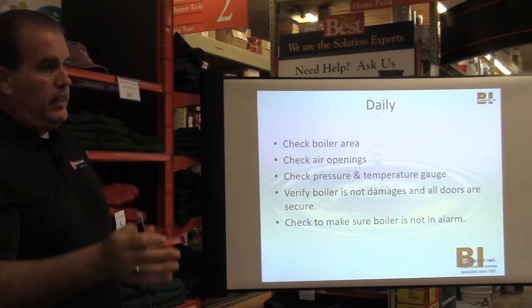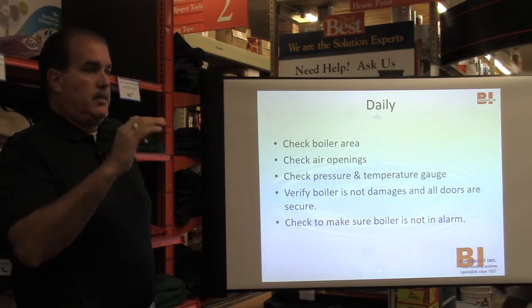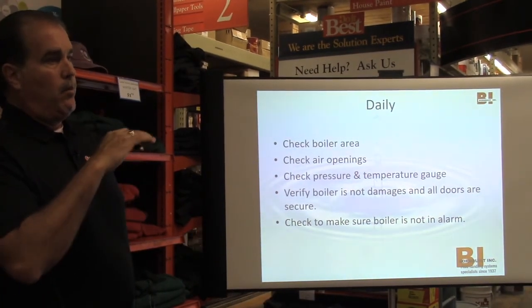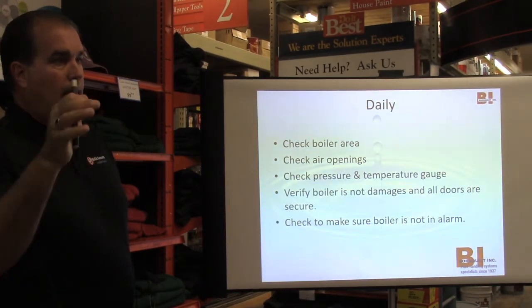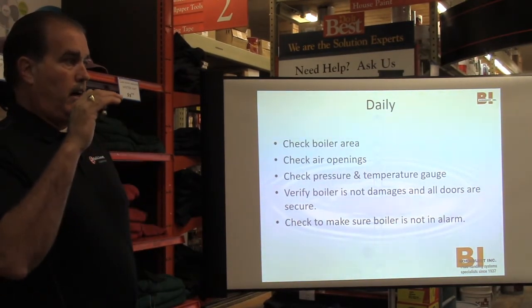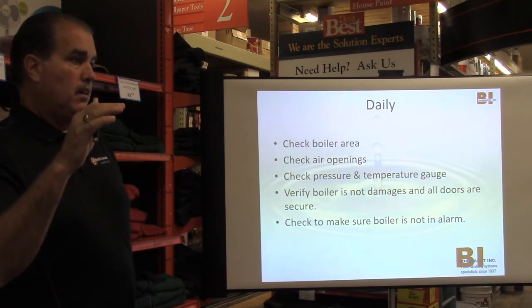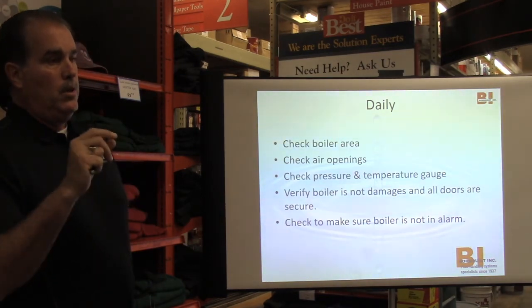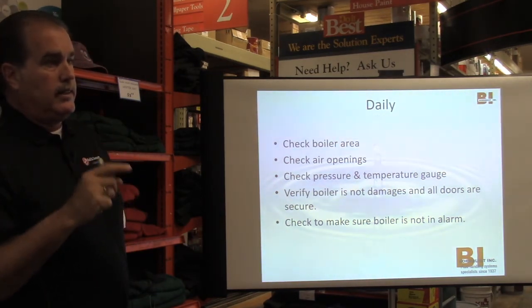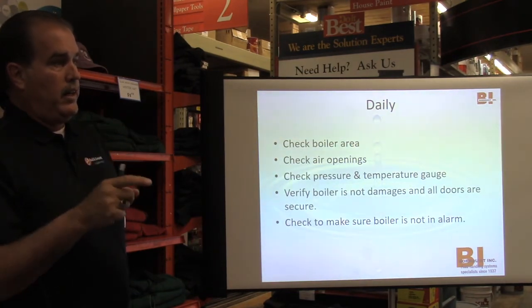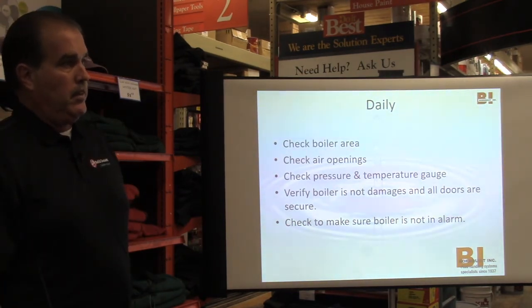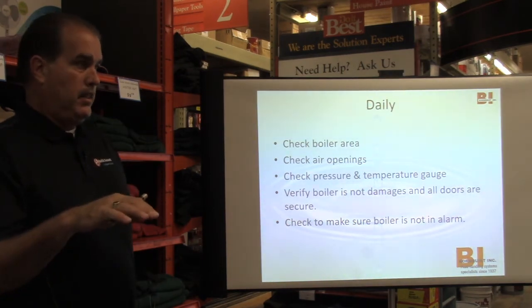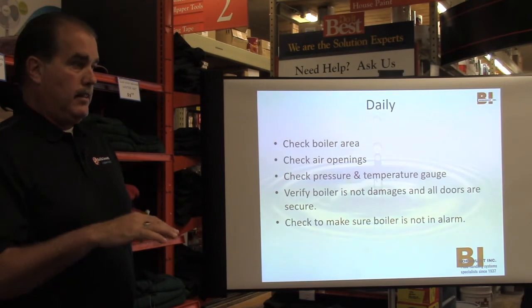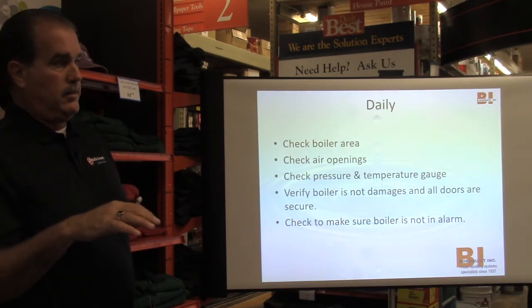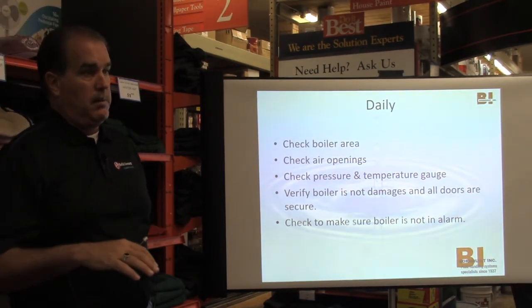Usually, if you're not getting heat out to your system, you've got a condensate management problem, where water condensate is getting trapped, blocking those radiators, or you've got radiator vents that are plugged up, blocking the air from getting out. Because if your radiator vents do not let the air out, those radiators will take a long time to get warm, if they get warm at all. So you've got to make sure. Air is the enemy in a steam system. Condensate can also be the enemy because it blocks the steam. But really, air is the big enemy in a steam system.